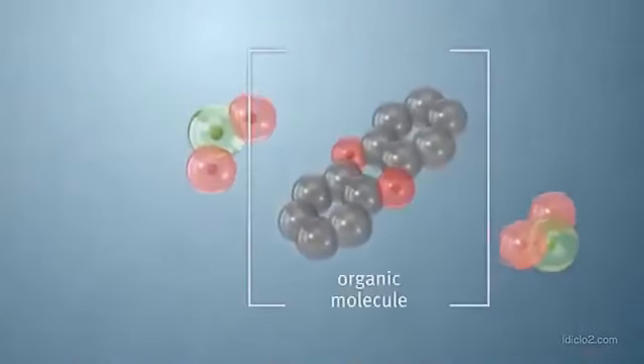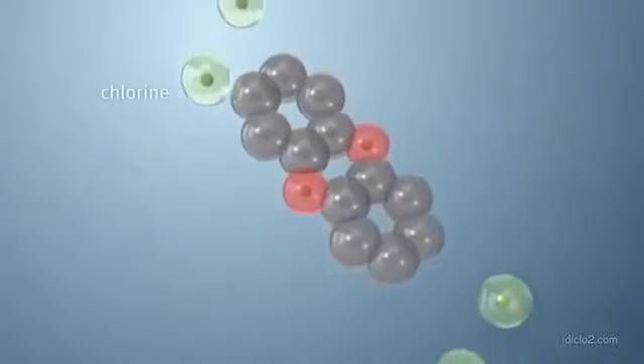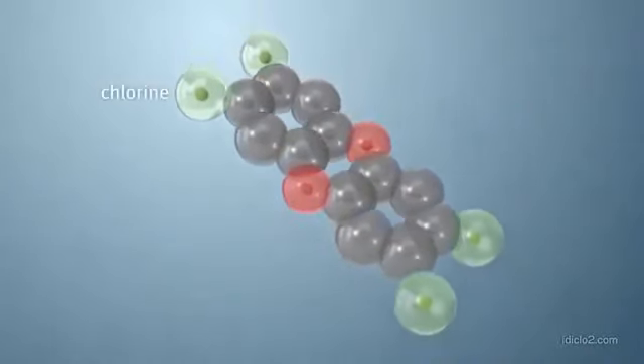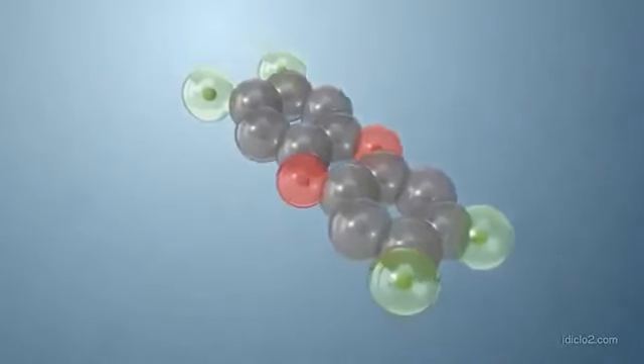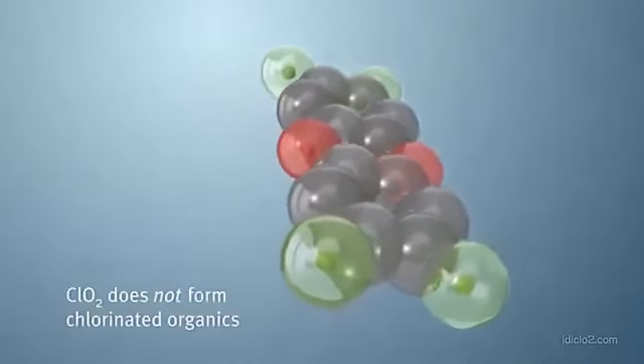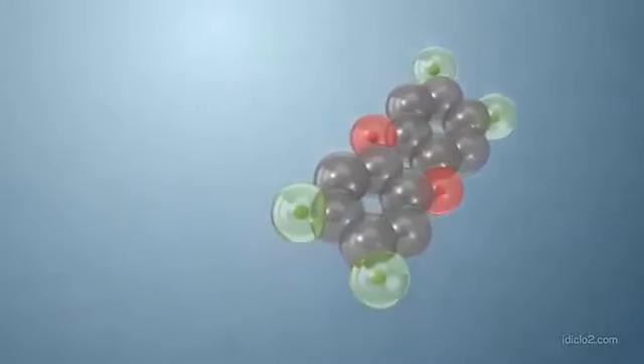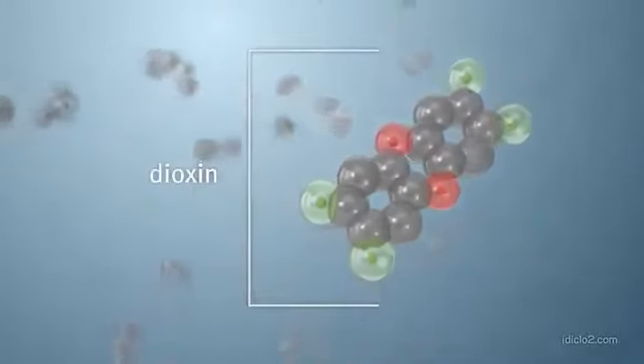Third, ClO2 does not chlorinate organic molecules as does chlorine. Chlorine can react by addition or substitution reactions, which incorporates a chlorine atom into an organic compound. This leads to the formation of harmful chlorinated disinfection byproducts, such as trihalomethanes, THMs, chloroform, and dioxins.